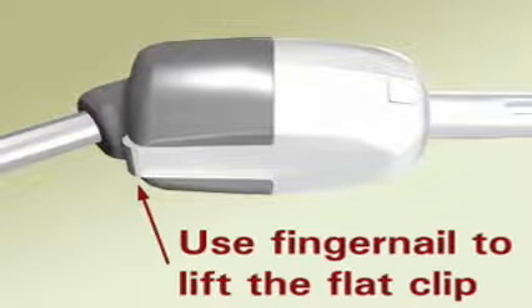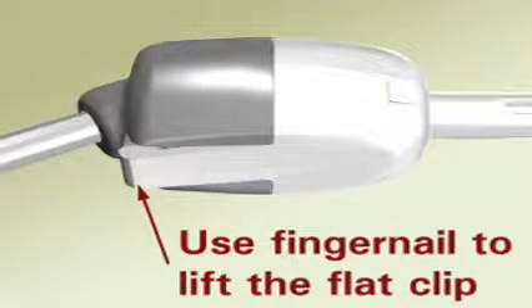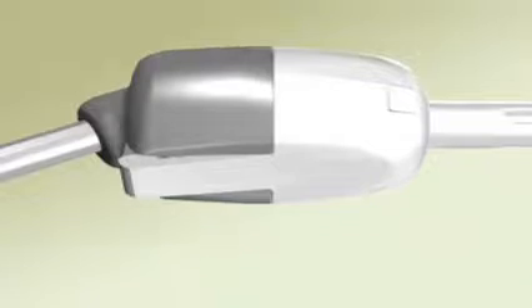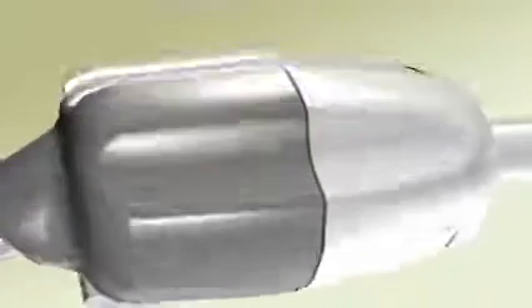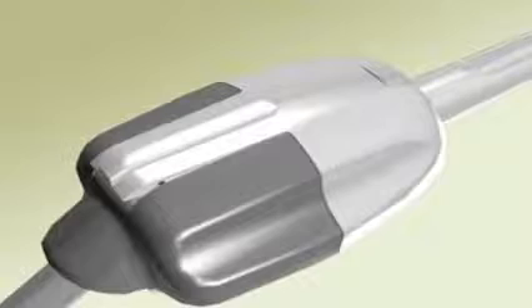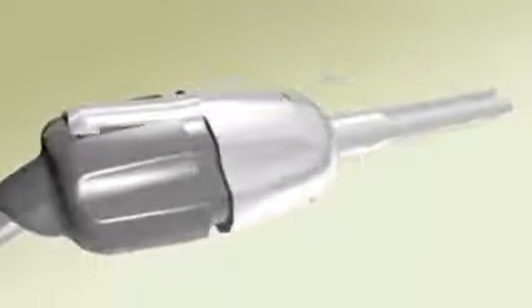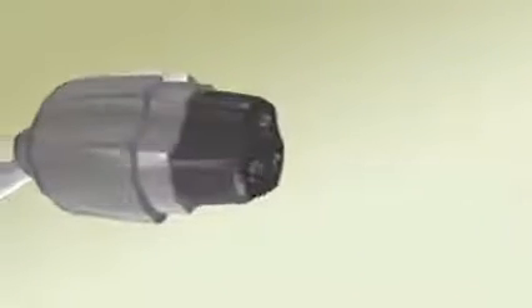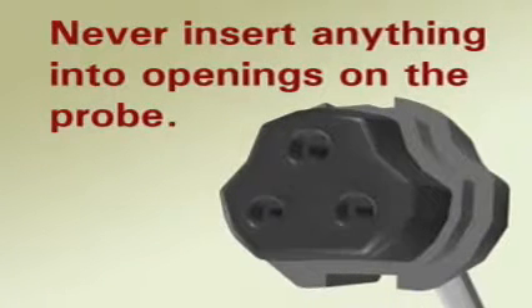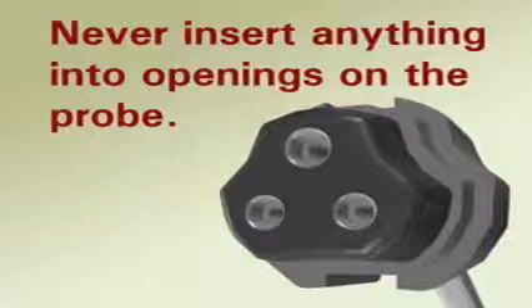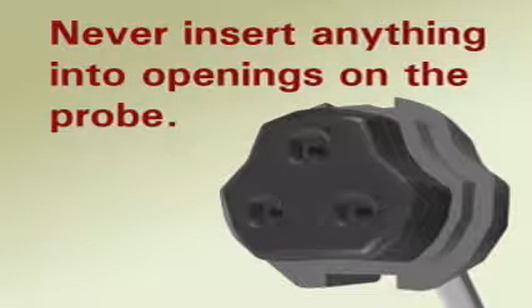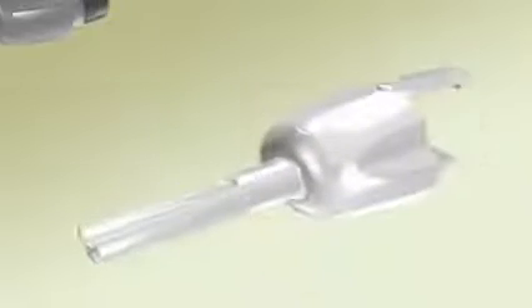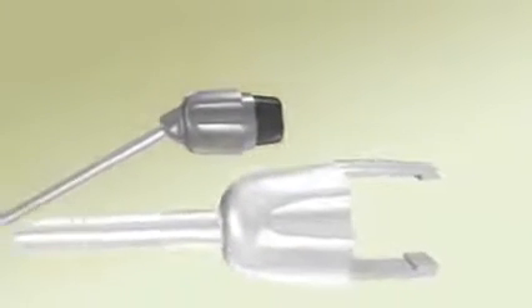Use your fingernail to lift up on the end of the smooth, flat clip to unlock it. Next, use your fingernail to lift up on the clip with the ridge and unlock it. After both clips are unlocked, gently pull the nozzle off of the probe body. Never insert anything into the openings in the probe body that appear when the nozzle is removed, as this could damage sensitive components.